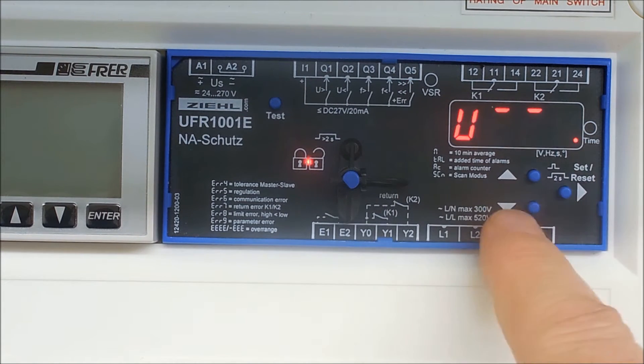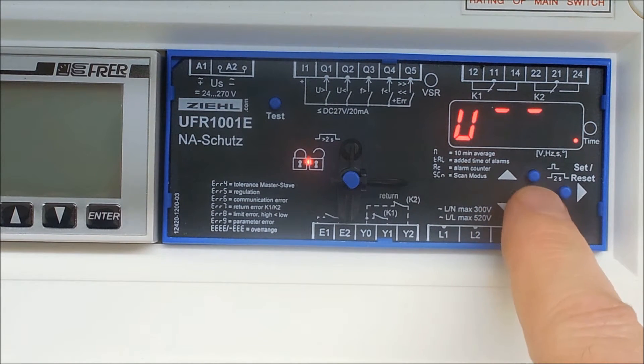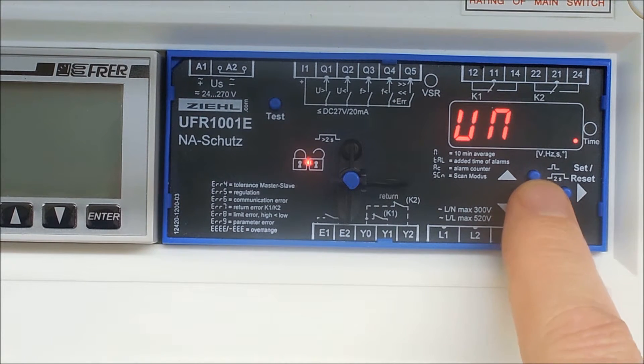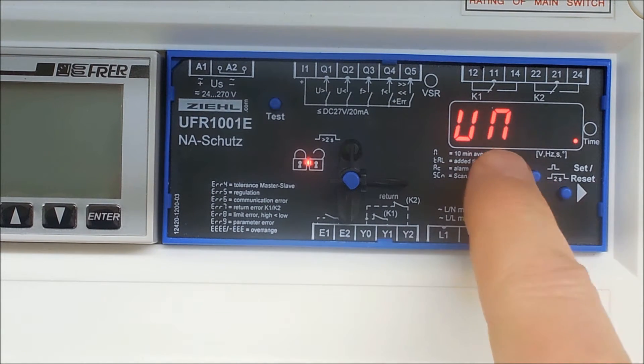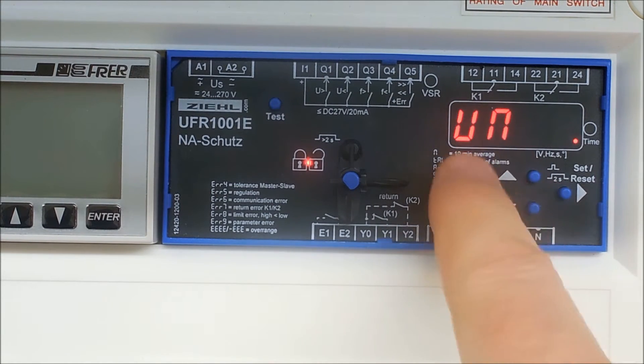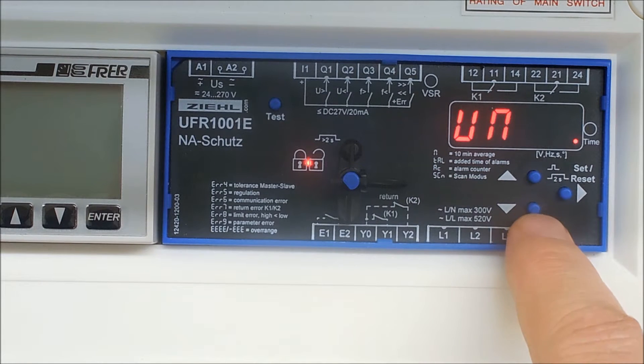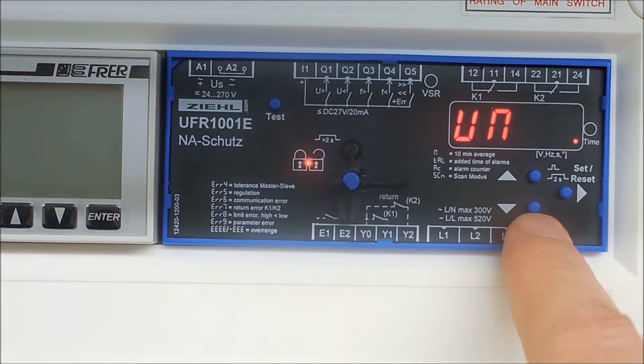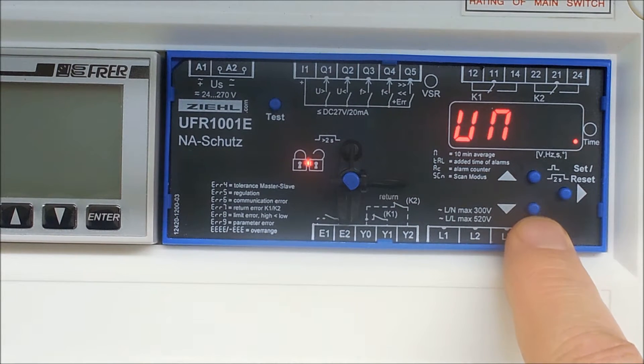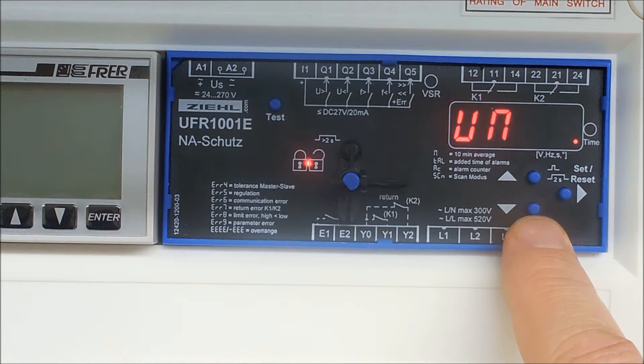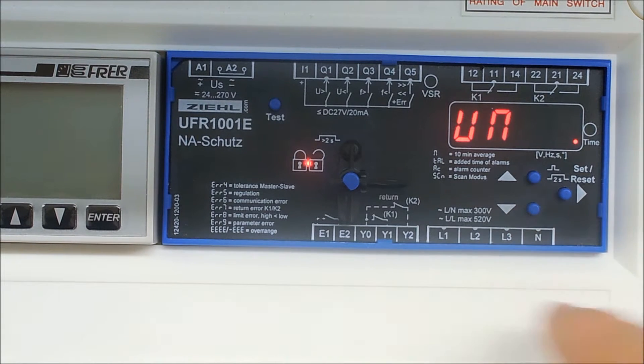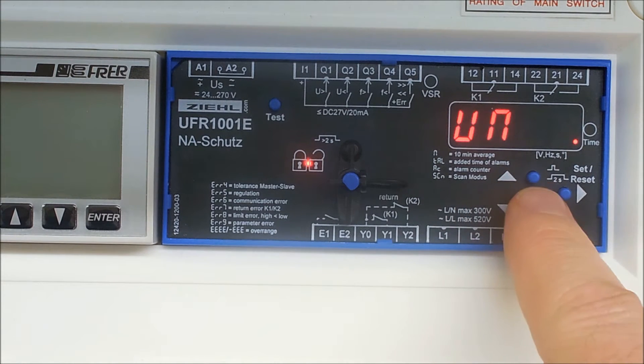So you have the second level voltage, you have the first level of over voltage, you have the value of the voltage is monitored and recorded every 10 minutes by the unit. So it gets the average quality of the voltage so you can see if you are getting spurious trips possibly what may be causing it.